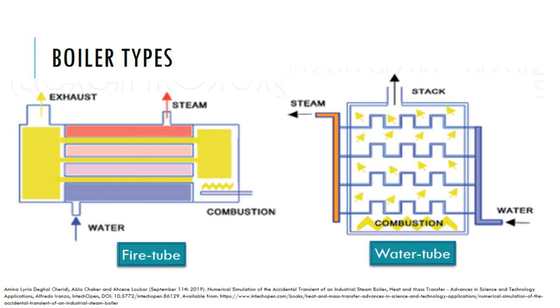Hence, if you look at an article talking about the types of corrosion in boiler, you will find mention of types such as general, pitting, acid, galvanic, etc. It is indeed true that you will find these types in both the boilers, but the manner in which this corrosion happens is different. For example, because the water flows inside the tubes, the chances of pitting aqueous corrosion are more outside the tube and in the internal regions of the fire tube boiler.